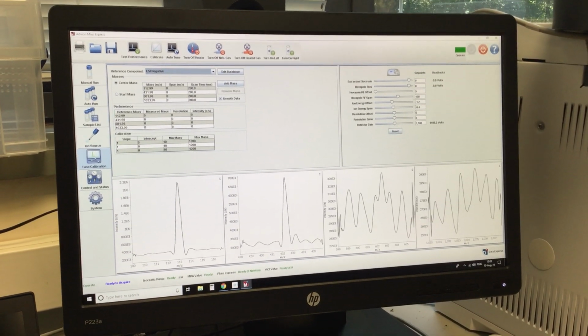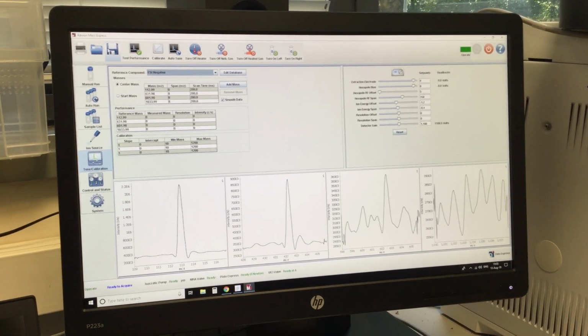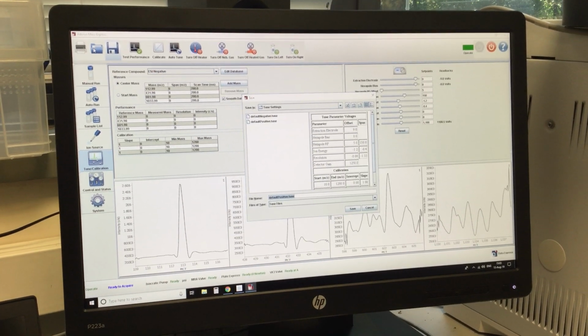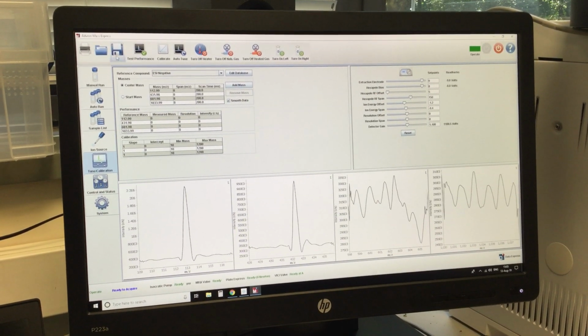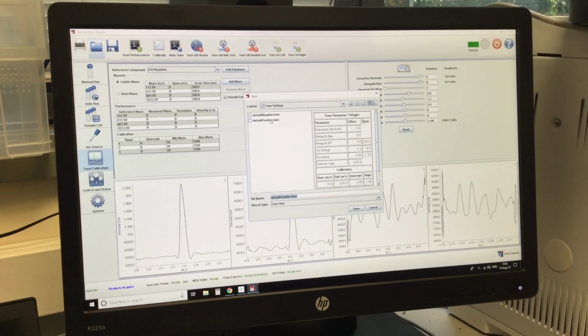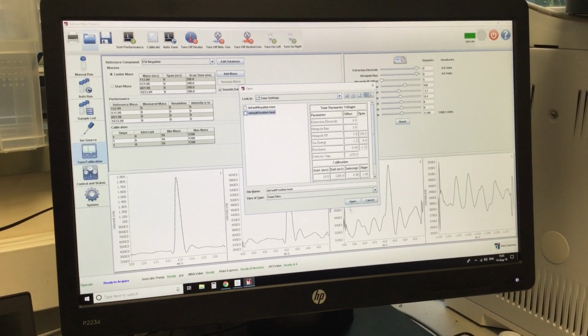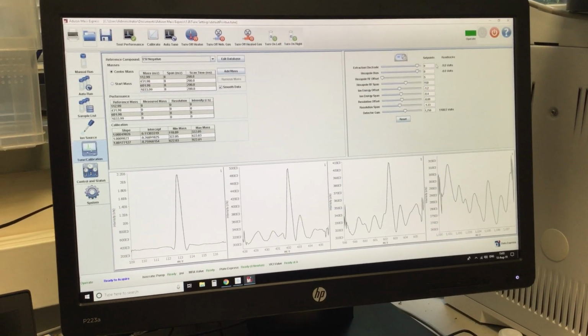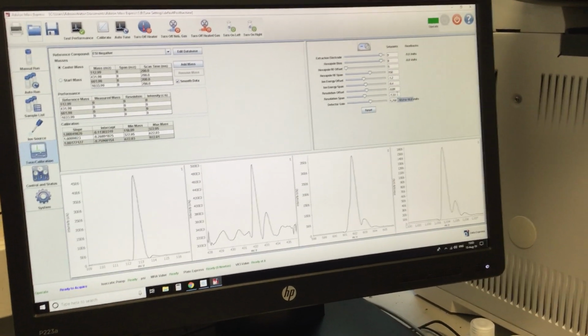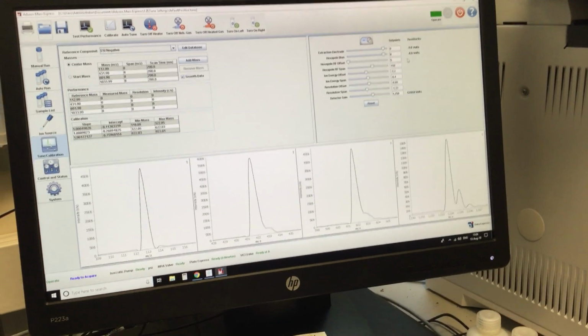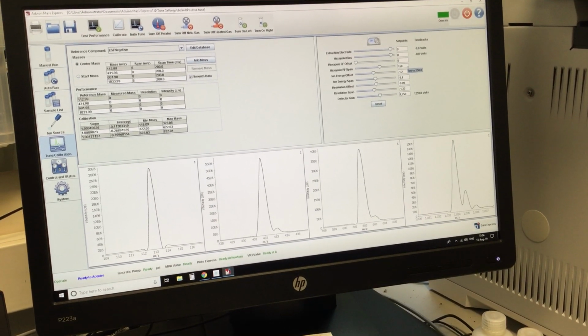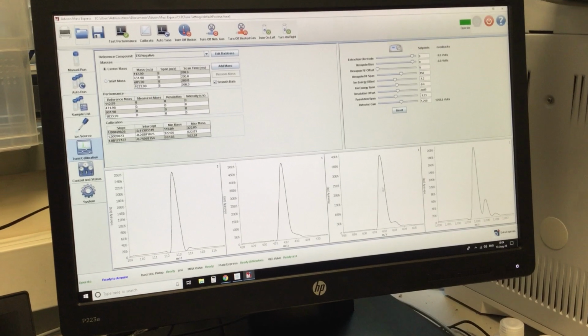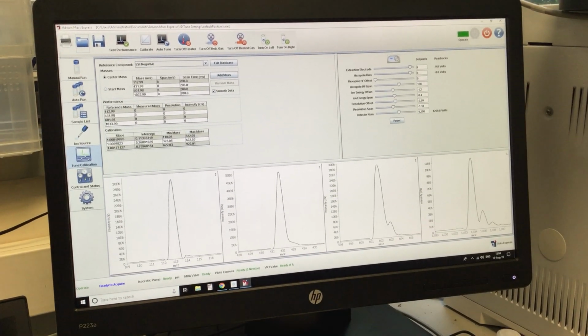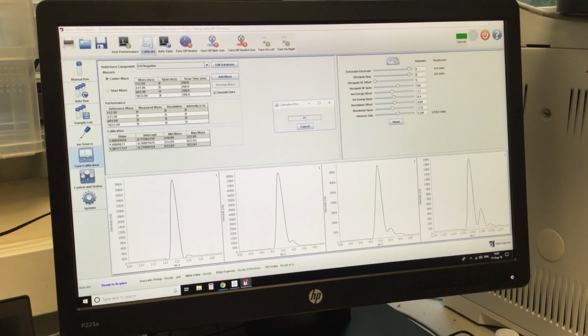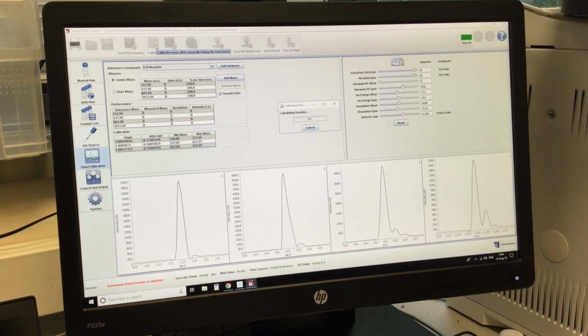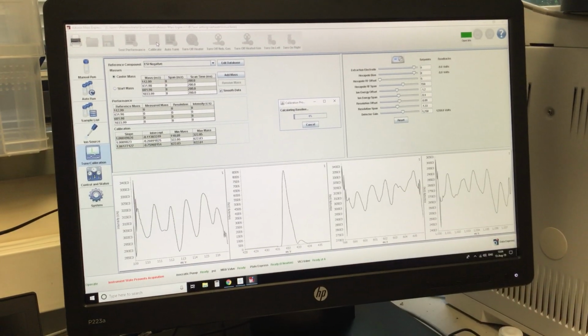So in order to bring up the correct values, I'm going to open the default positive file. So these are the same values that I used in positive, but now they've been changed to negative values. And so now I've got my peaks, and I can do the calibration again. So now it's going to do the calibration in negative ion mode for the negative ion reference peaks.